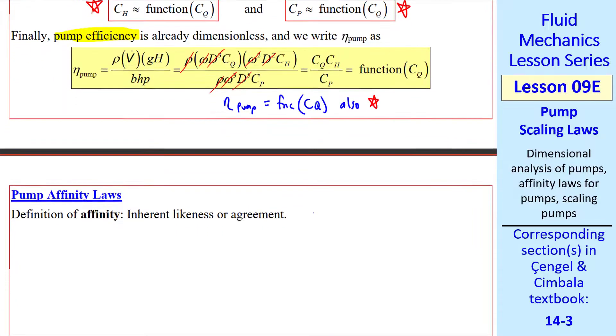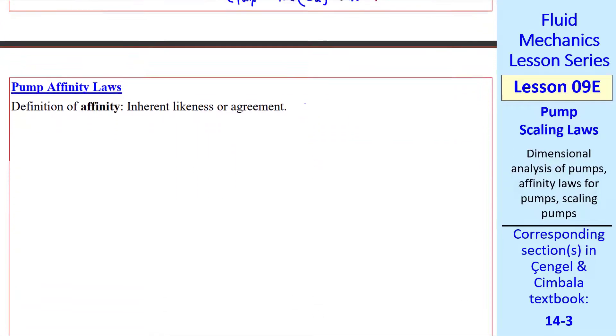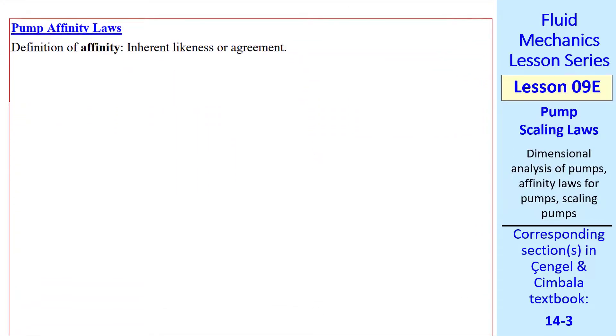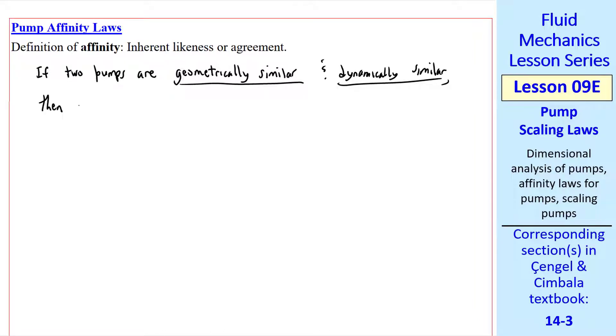Turbomachinery engineers like to talk about the pump affinity laws. I looked up affinity in the dictionary. It's defined as inherent likeness or agreement. So we'll use it this way. If two pumps are geometrically similar and dynamically similar, which by review means that the independent pi's are equal between the two pumps, then their pump performance curves fall on top of each other when plotted non-dimensionally. Here's an example.